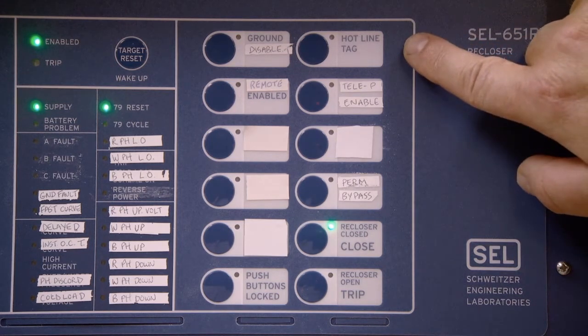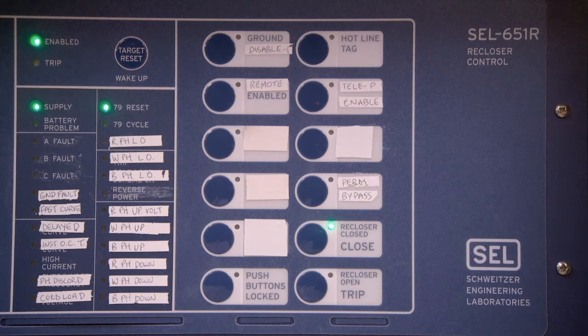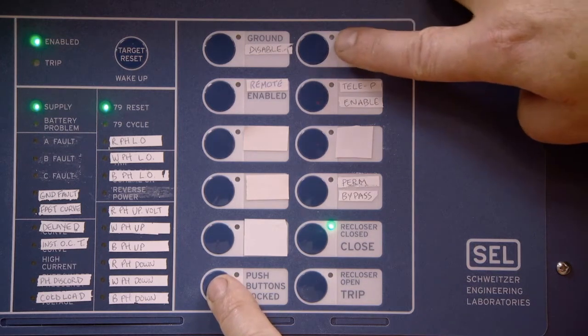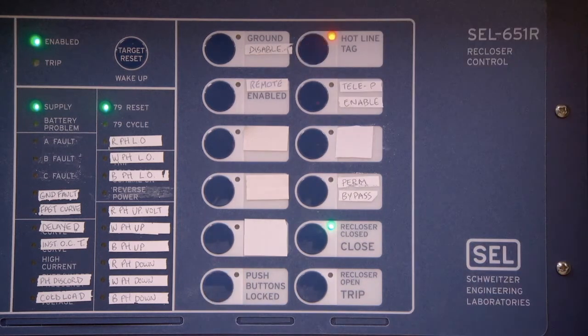Hotline tag. This is used to set the control and recloser for one fast operation to lockout. This is for equipment protection. To apply this, push both the push buttons locked and hotline tag buttons simultaneously. The hotline indicator will turn amber.